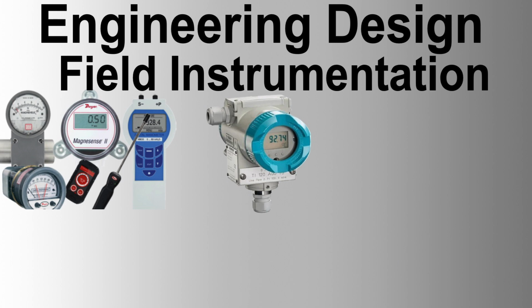Where remote transmitters are required, the element head must be weatherproof to IP65 and certified to EExd. The RTD enclosure material must be SS316 with metric M20 cable entry. The RTD sensor burnout response must be selectable as either upscale or downscale. The temperature elements to be used at the block valve stations on the pipeline must be clamped or glued to the pipeline to measure both metal and fluid temperature.